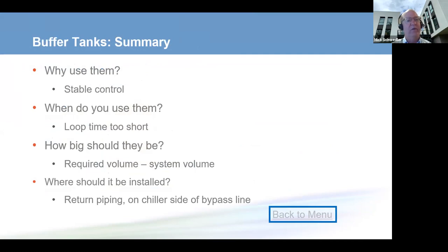What this allows us to do, this gives us stable control. If our loop time is too short, we install it on that return side and we install enough capacity to get us up to our required loop time. The other thing I like to share is that once you're required to put a buffer tank into the system, it usually doesn't cost a lot more to make it a little larger. So a little bit more volume, while not required, generally will give you, especially on small chillers and chiller plants, more stable system control. Not chiller control, but the system will operate more smoothly.